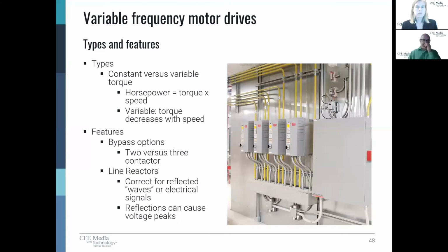We have a variety of options as well, whether or not we want contactors, and the contactors, 2 or 3, is how do I want to isolate that VFD? And do I want to isolate the feed coming in and leaving simultaneously? A 3-contactor bypass is the easiest way to isolate that VFD.